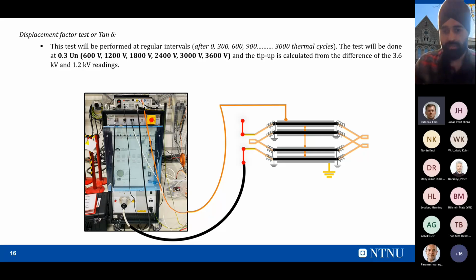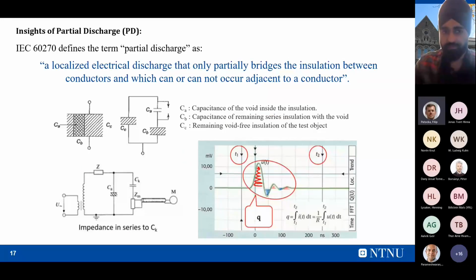After this, what do we mean by partial discharge, another measurement? As I explained earlier, any dielectric material is shown as a capacitance, but if there is a small void inside that insulation, that void has some gas, and that gas usually has a breakdown strength which is less than the breakdown strength of the dielectric material. That is also shown in the electrical circuit: if there is a small void here, with some gas inside it, it will also be represented by a capacitor.